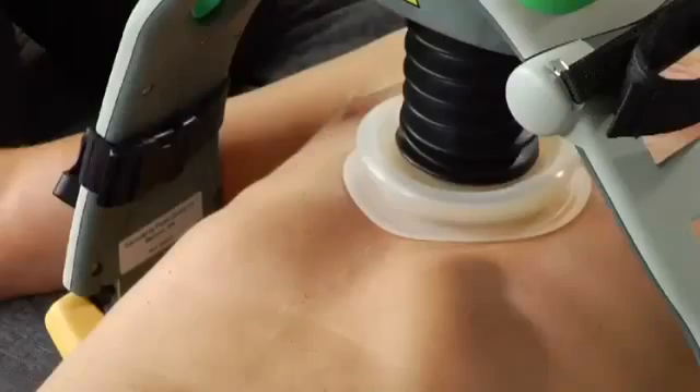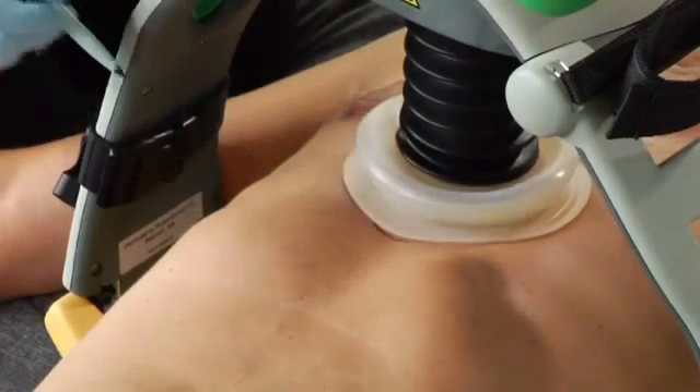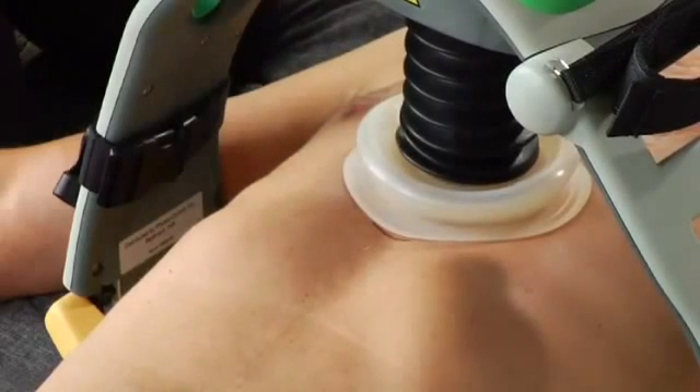When Lucas is operating, your fingers should not be on or below the suction cup. If you want, you can mark the right position on the patient's skin. With a mark, you can easily see if the suction cup shifts and you need to reposition it.